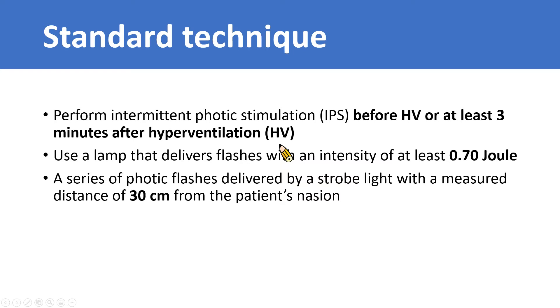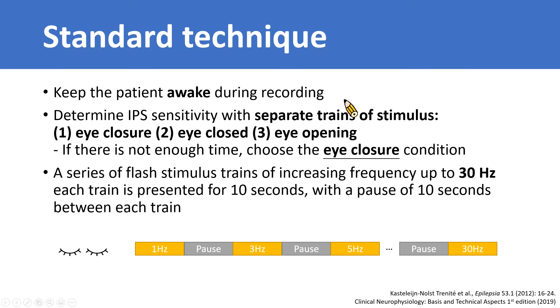To standardize the IPS recording, we should use a lamp with an intensity of at least 0.7 J that delivers a series of flashes by a strobe light 30 cm from the patient's nasion. We should keep the patient awake during IPS recording, because IPS during sleep does provoke photoparoxysmal responses only in REM sleep, which is usually not obtainable during a routine EEG recording.